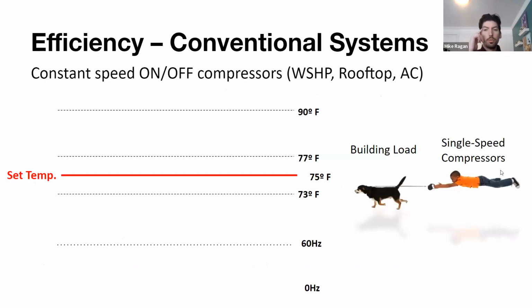All right, so now we're going to break down the advantages of having an inverter-driven compressor. That's the type of compressor we're utilizing on heat pump technology. It allows for variable speed on that compressor. First off, I'm going to talk about conventional speed compressors. These are single speed compressors. It's either fully on or fully off in operation.